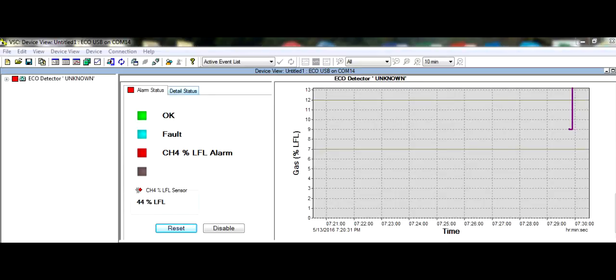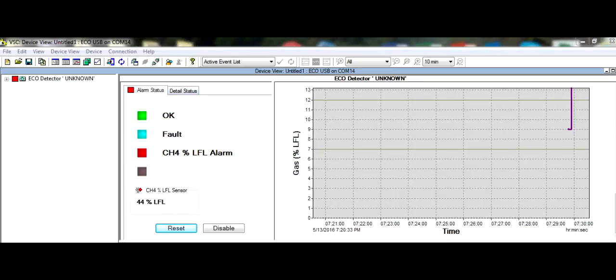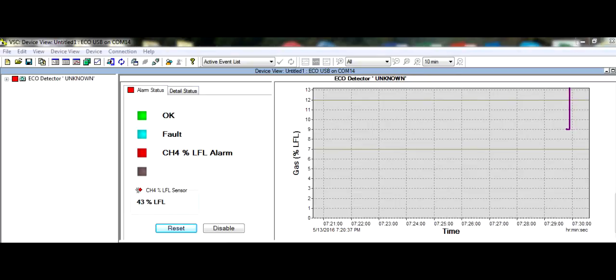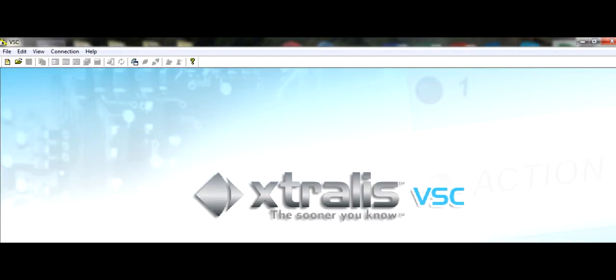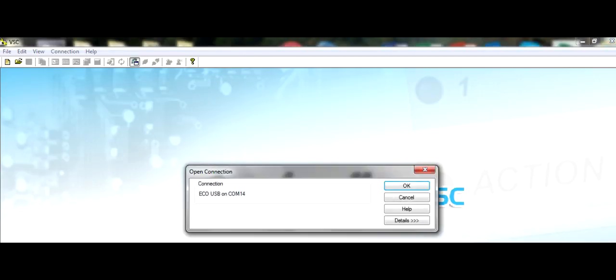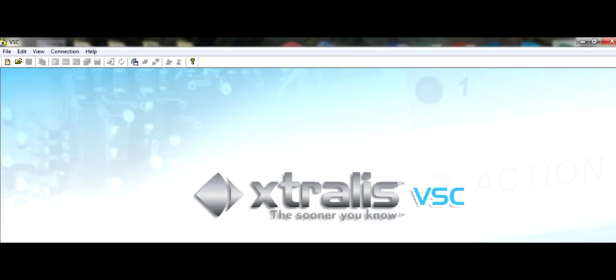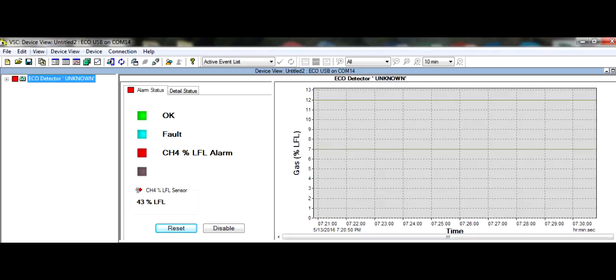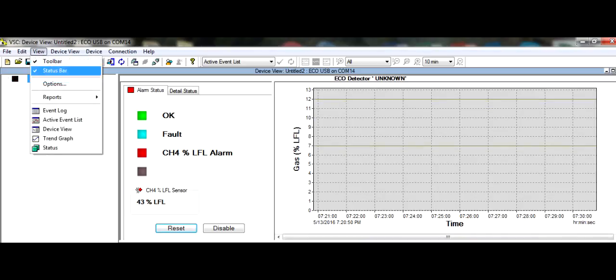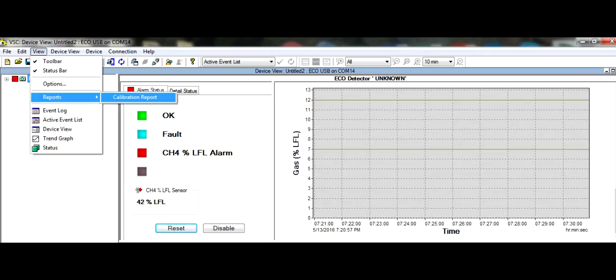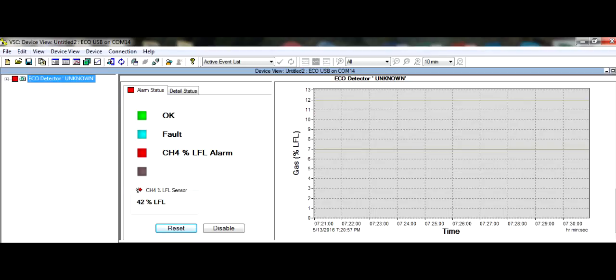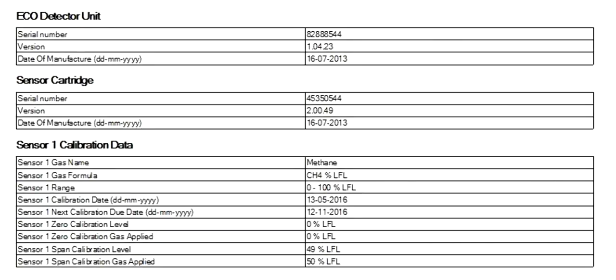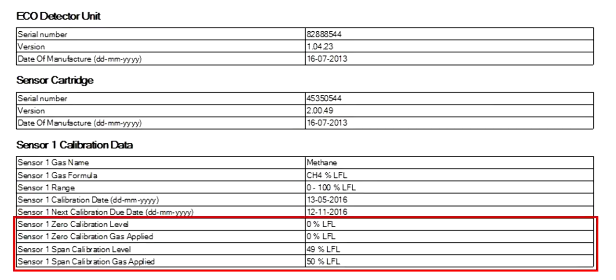Finally, you must generate a calibration report. To obtain the updated calibration report, you first must log out of the detector. Then, log back on. Highlight the detector, then go to View. Go to Reports, then select Calibration Report. This will generate the calibration report. The top of the report contains detector specific information. You must verify the span gas calibration level is within 10% of the gas applied. If not, you must recalibrate the detector.